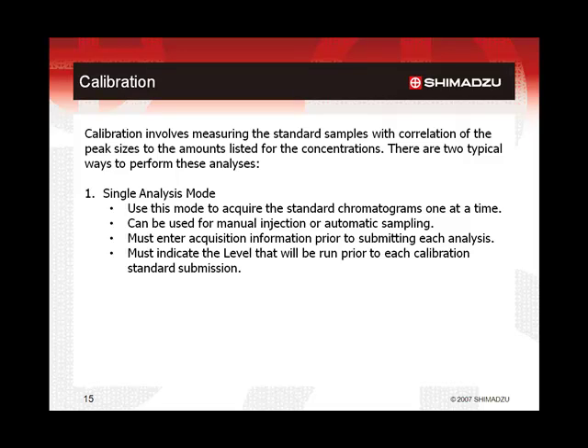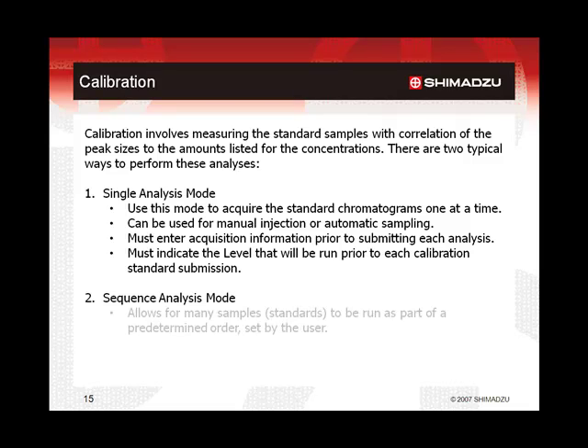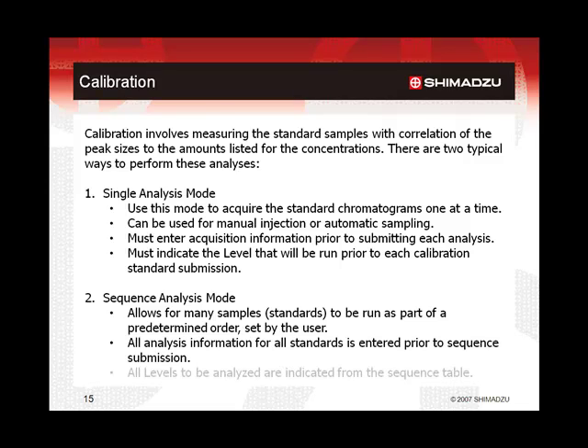The sequence analysis mode allows for many samples, including calibration standards and unknowns, to be analyzed as part of a predetermined series defined by the user. The sequence table contains all of the acquisition information for all samples, including the standards. With an automatic sampling system, this permits the samples to be run without immediate interaction from the user. All standard level designations for fully automated calibration should be entered before running the sequence.